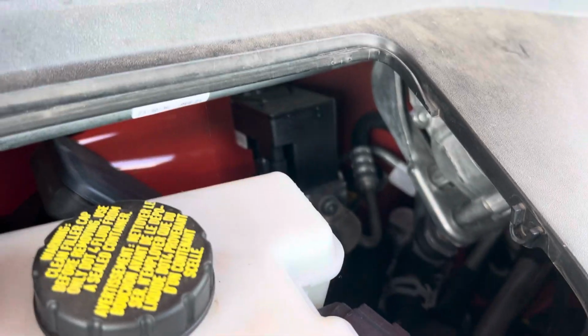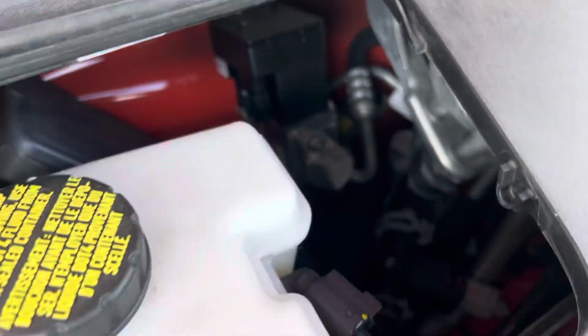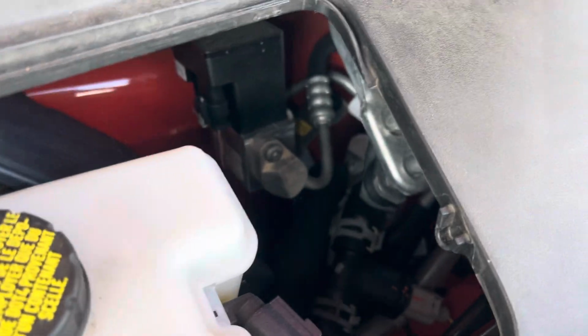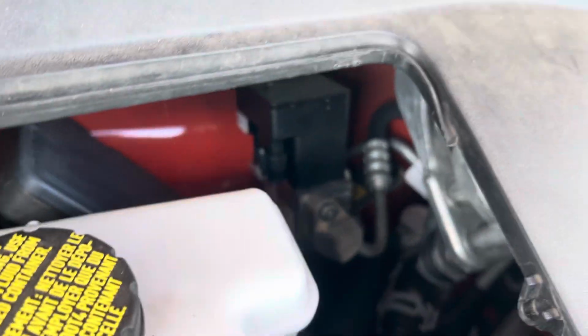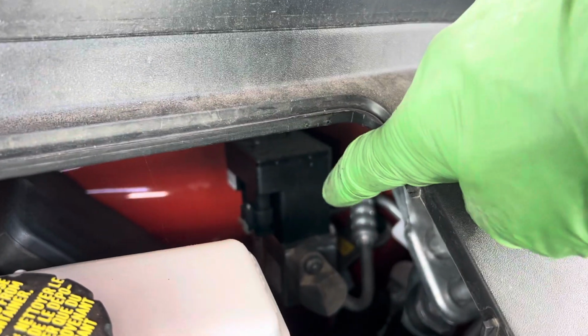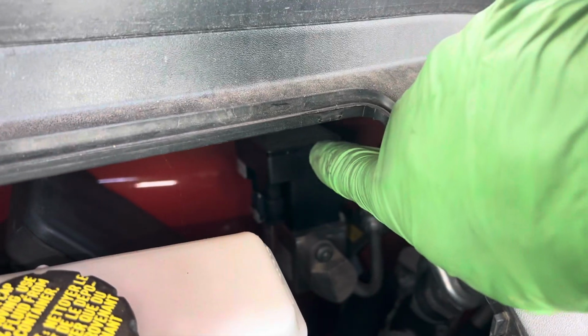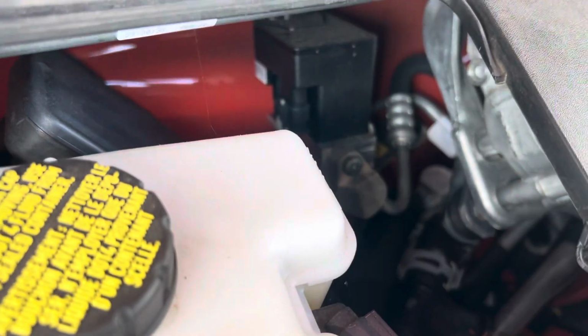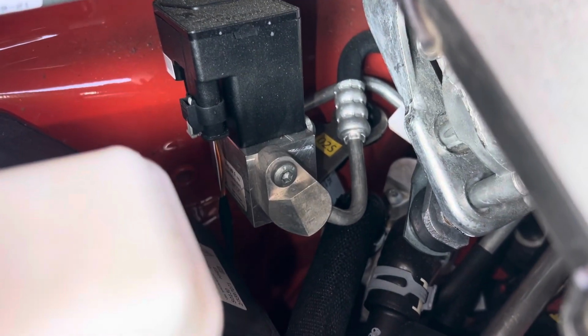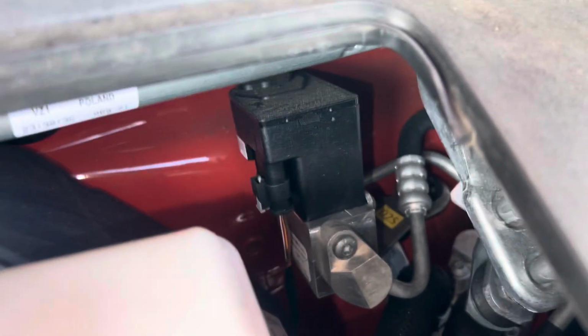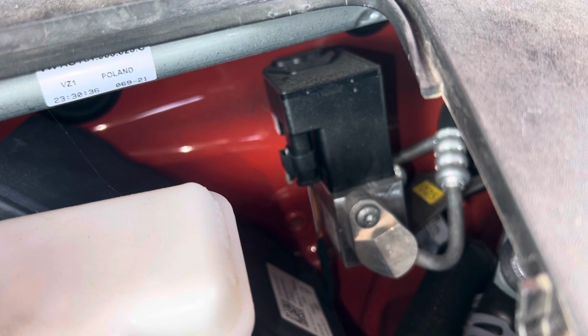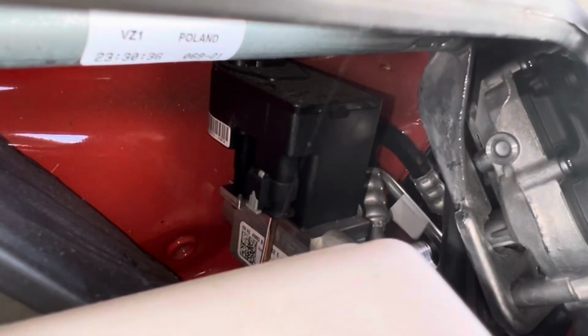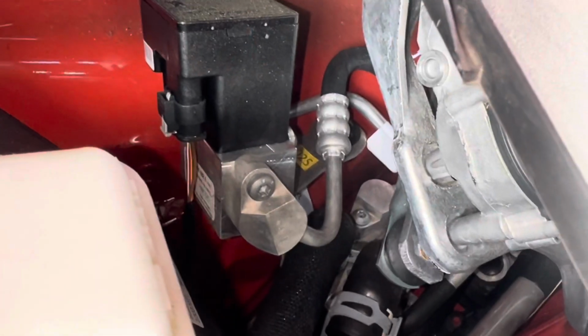We're back on this 2021 Porsche, and I'm trying to follow the refrigerant line circuit. It's an electric vehicle. Here we've got what looks like an electronic expansion valve right there, a metering device. Do you see the liquid lines right there? That's not a simple, it's a 3-wire, so it's not a simple on-off solenoid. By looking at the shape of it, it literally has some valve gearing inside, it meters.